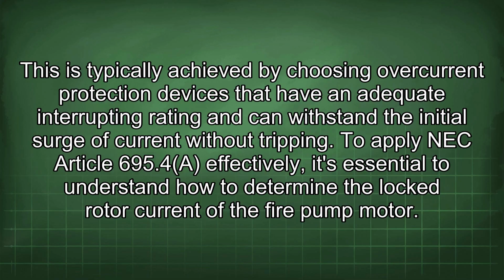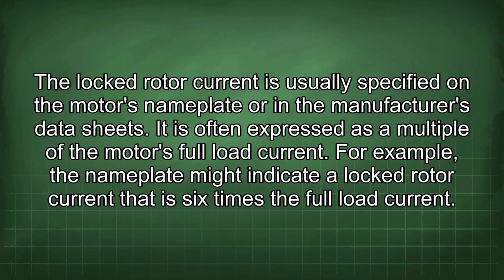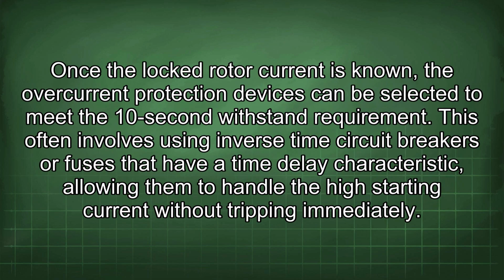To apply NEC Article 695.4 effectively, it's essential to understand how to determine the locked rotor current of the fire pump motor. The locked rotor current is usually specified in the motor's nameplate or in the manufacturer's data sheets. It is often expressed as a multiple of the motor's full load current. For example, the nameplate might indicate a locked rotor current that is 6 times the full load current. Once the locked rotor current is known, the overcurrent protection devices can be selected to meet the 10-second withstand requirement. This often involves using inverse time circuit breakers or fuses that have a time delay characteristic, allowing them to handle the high starting current without tripping immediately.